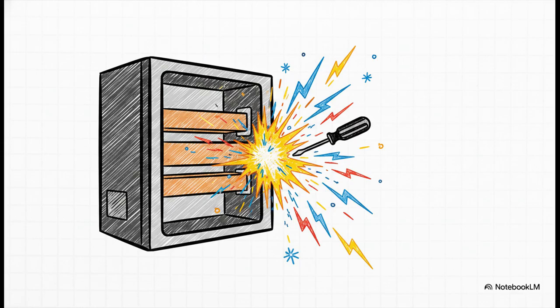These power plants are built to dump massive, sustained energy to keep networks alive during disasters. So, if you accidentally drop a screwdriver into a bus bar, which is the main copper highway of the power cabinet, the heat generated can instantly weld that tool to the terminals. That causes a severe electrical fire or a blinding arc flash. It is a terrifyingly unforgiving environment.